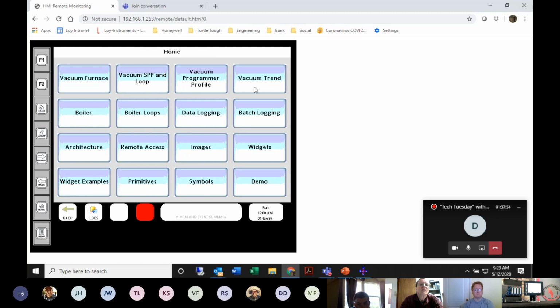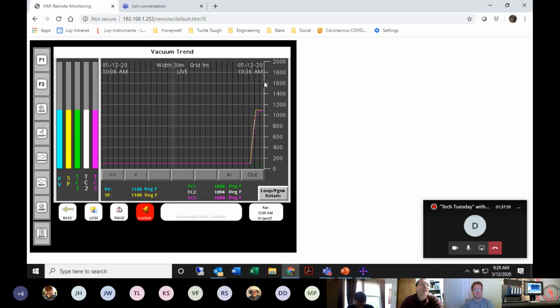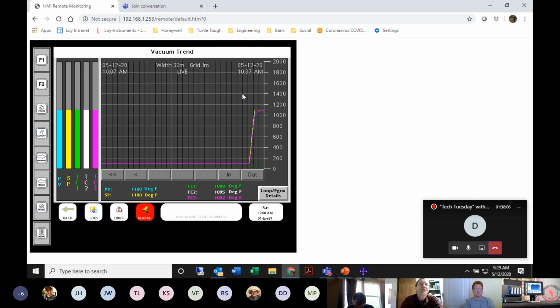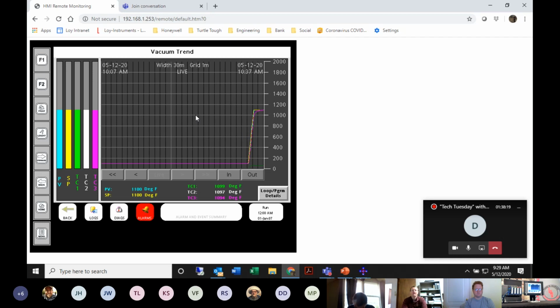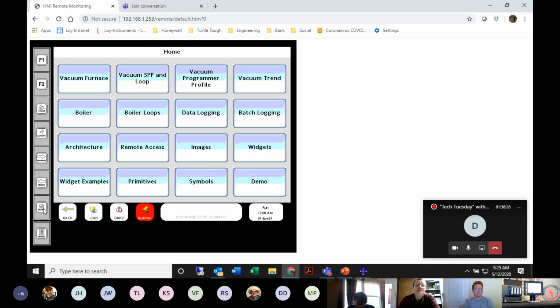We have other displays, like vacuum trend or trending displays. These basically mimic the process recorder that you would have on the front of the panel. You can build trend displays into the HC900, and then store those trend displays as a CSV file, or push those trend files out to a server location, and have the HC900 be not only the process controller but also the recorder, built into one process system.